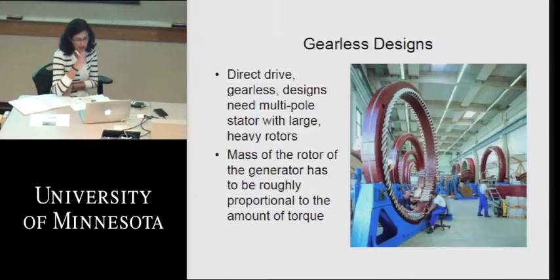Next slide. But there are gearless designs. Enercon, Repower, and other manufacturers try to produce a gearless design. It's a fundamental design decision you make of how you're going to start building a wind turbine. If you go gearless, you obviously save the wear and tear and the maintenance of the gearbox. But as you see, these generators now have to be multi-pole because you're not stepping up speed. One of the reasons we step up the speed to 1,200 or 1,800 RPM is that we can put more power in a smaller footprint, in a smaller generator.